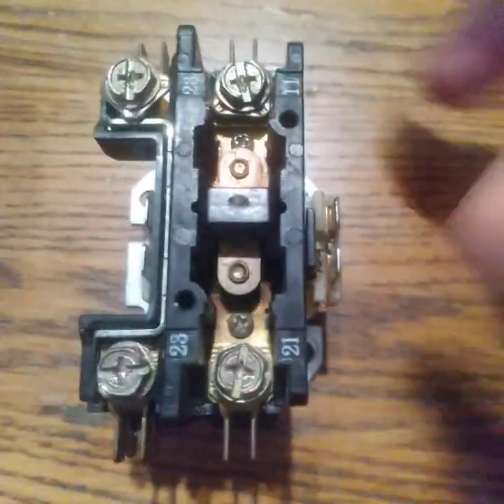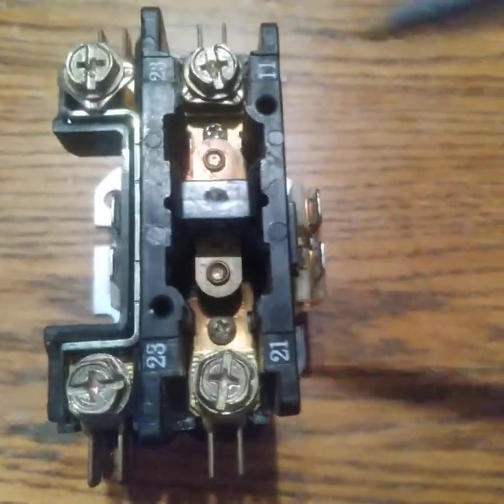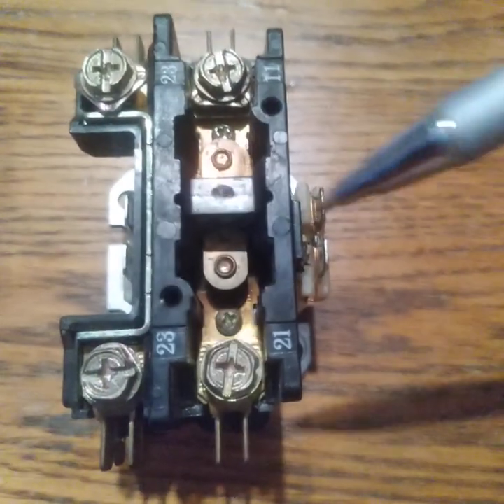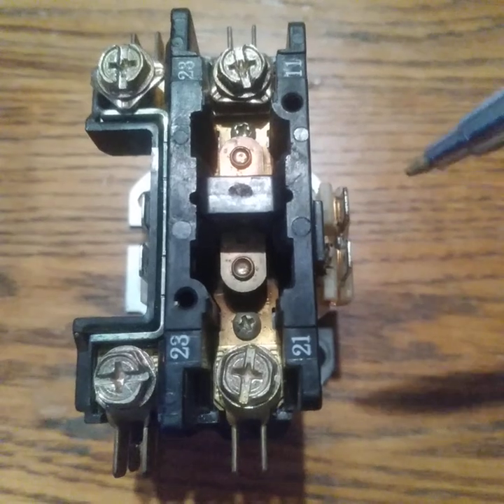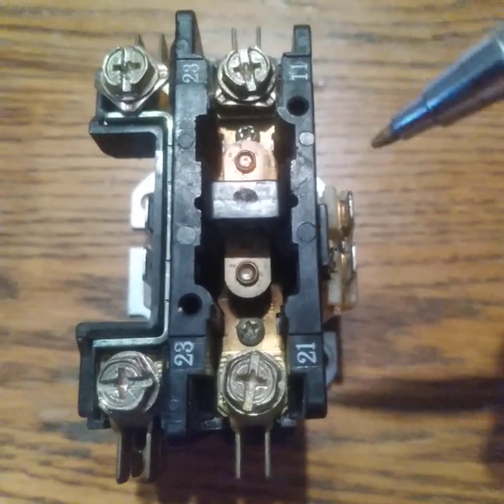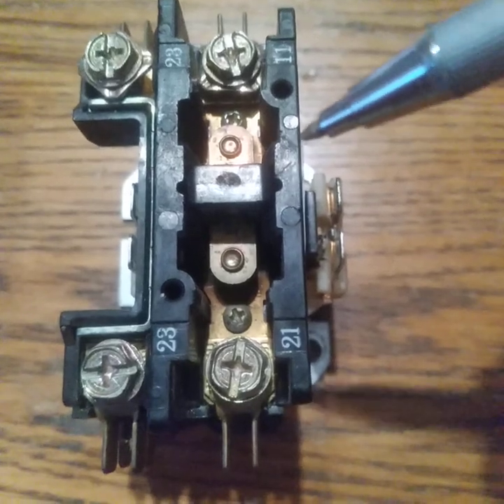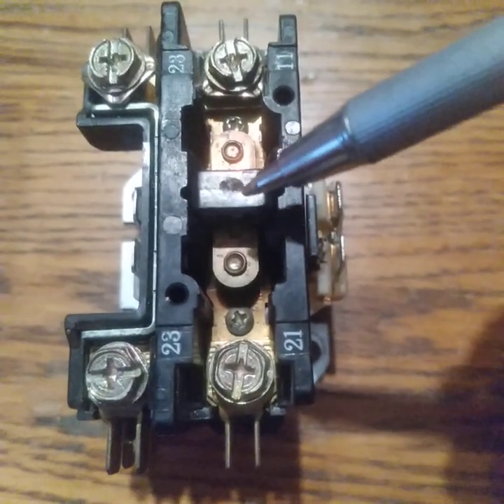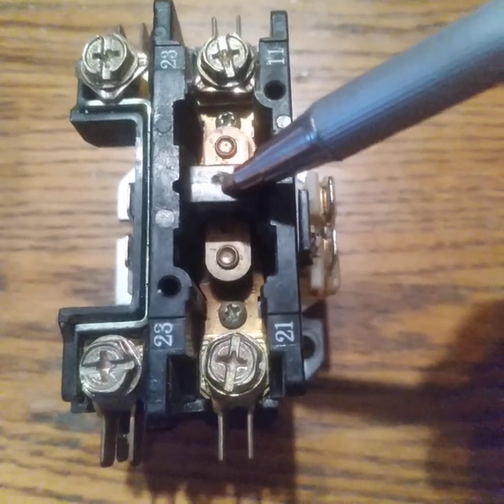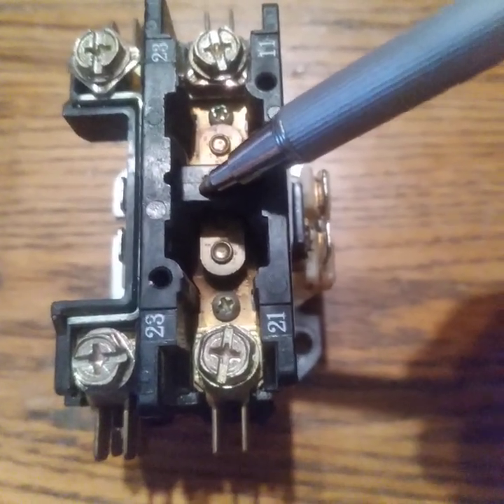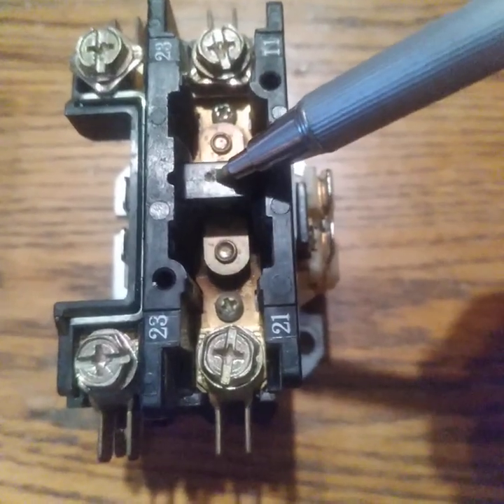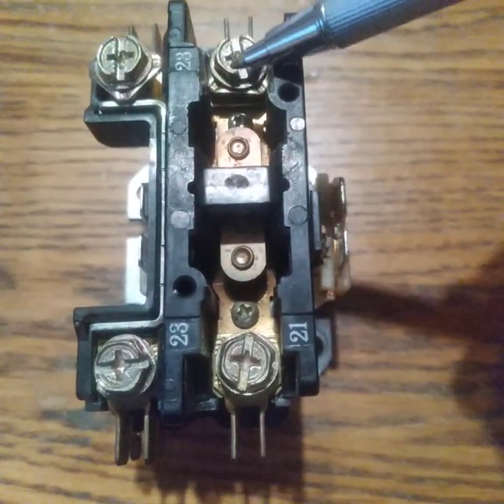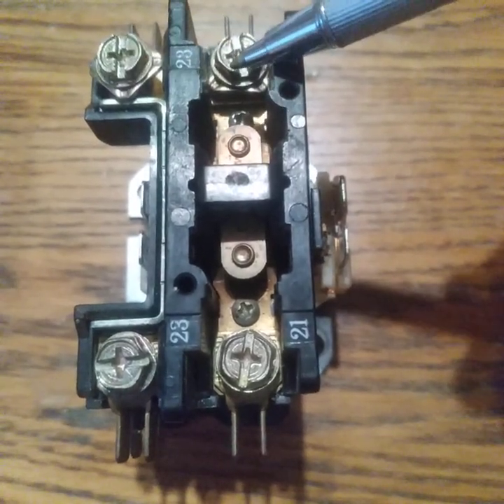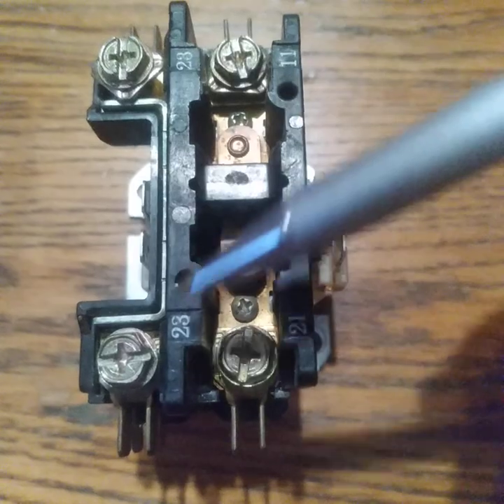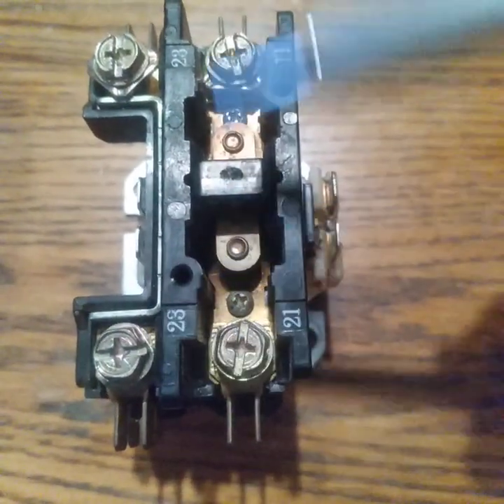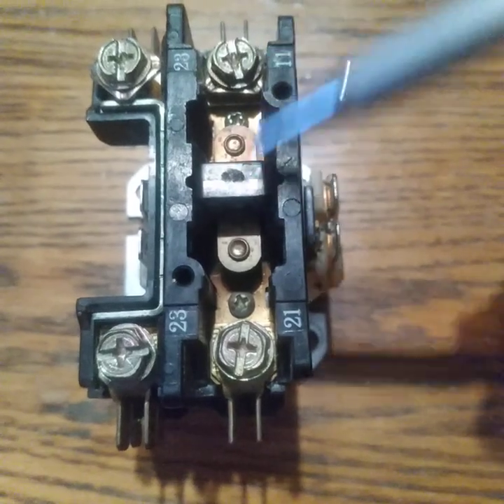Now, on the side here, you see these prongs in this coil. These are for your low voltage. The low voltage wire would feed here and here. Once the low voltage energizes this contactor, it could even have a low grade buzzing sound, but when it does, this contact should come in. It should pull in and create maybe a magnetic field. When it does, this leg and this leg are energized. So now the voltage from L1, L2 goes to T1, T2, jumpers it off.